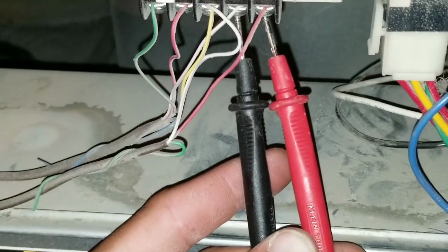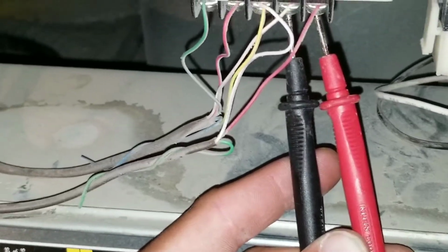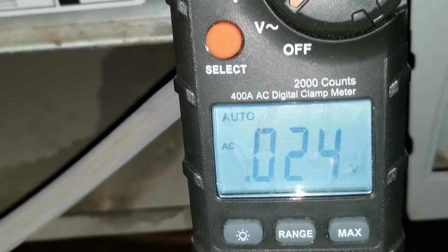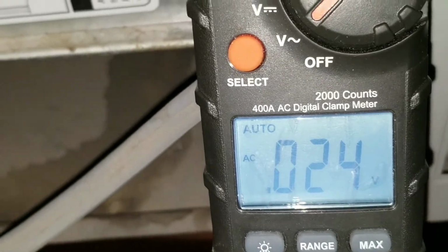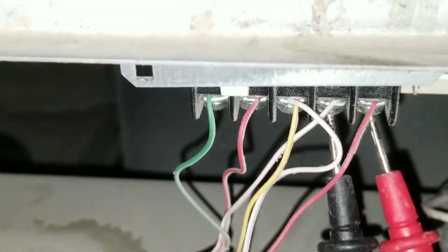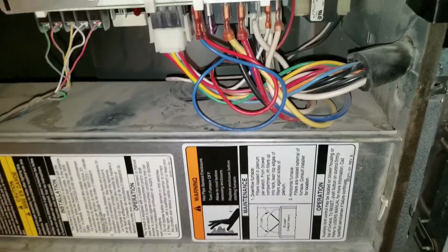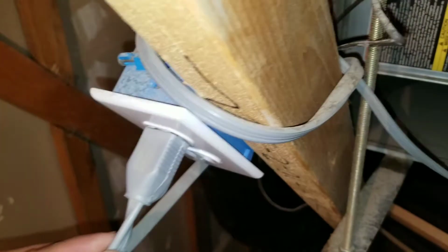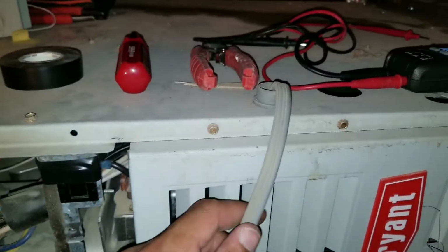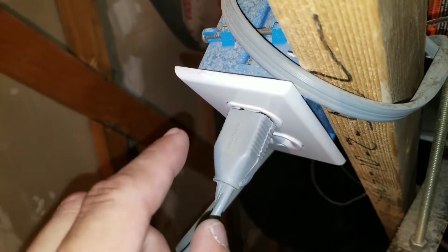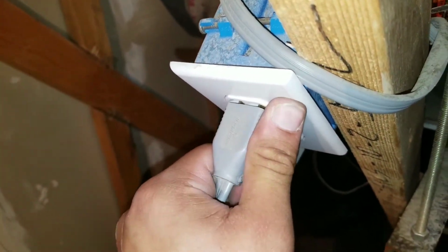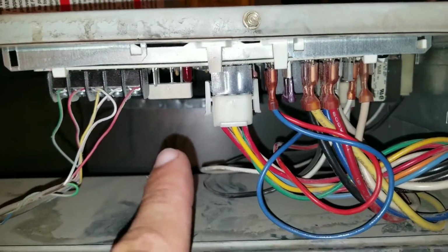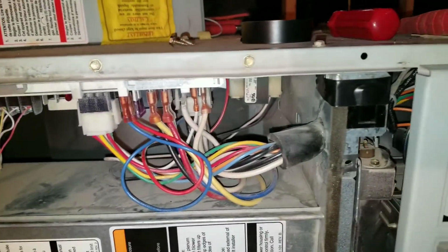Right now I'm just checking my low voltage wiring, and I've checked all the terminals, and you can see here I am not getting any voltage coming to my low voltage wiring on my terminals. Now I'm going to remove the power to my system. So here I have an outlet. This is basically supplying my 120 volts going into my system. You may have something that's a switch. Go ahead and turn that switch off. But on this one we're going to pull the power. And you can see here my board is no longer lighting, so I do not have power going to my furnace.